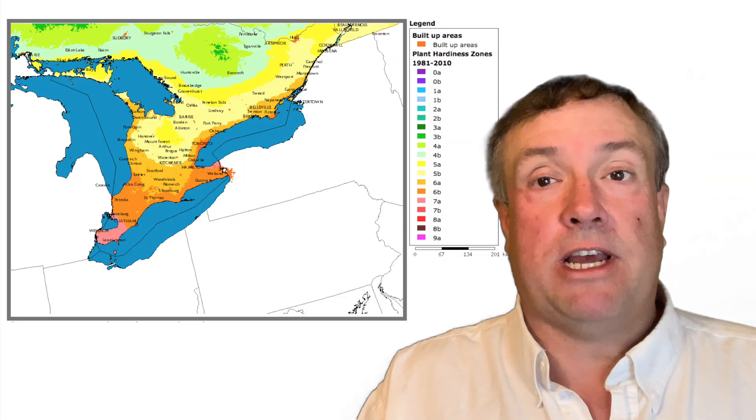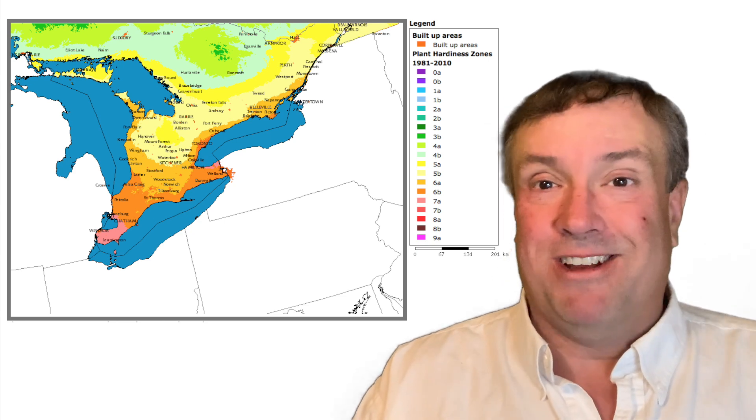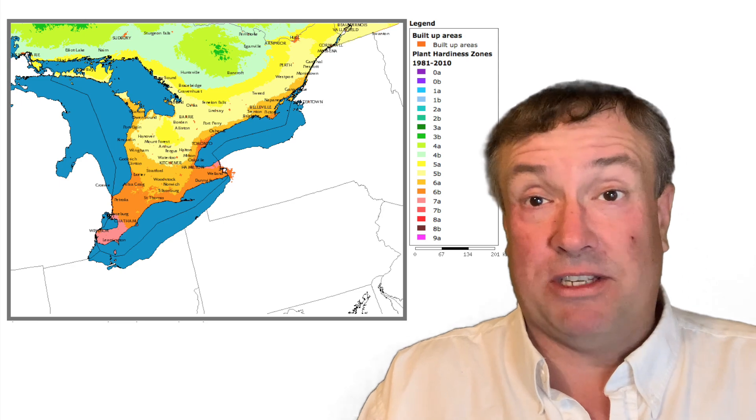Toronto, Canada is in a zone six, which is kind of a middle-of-the-road zone. Near Toronto you'll find a lot of Canadian agriculture, especially greenhouse agriculture. It does go below freezing — it is Canada — but we don't get Winnipeg winters in Toronto. Expect to go minus 10 to minus 20 Celsius. Your heating system should be able to accommodate that with good double pane glazing and insulation. Most greenhouses in Toronto are heated by natural gas, and there's an enormous industry creating vast amounts of fruits and vegetables in that area. Cooling is mostly done by shade cloth and large ventilation systems.